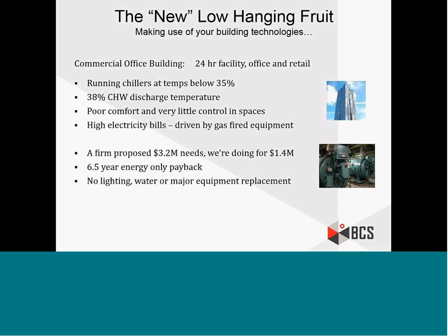When we managed that load better, that enabled them to direct their chillers a bit and enabled us to utilize that plate and frame a lot more. So they're going to drive a significant amount of savings—about a 6.5-year energy-only payback on the project. It really came through getting the right information and finding the low-hanging fruit that existed within their system, with just minor upgrades. Now they'll have a much better comfort level, a great handle on their equipment, and be able to maintain the building much better than in the past. So it's great for them.